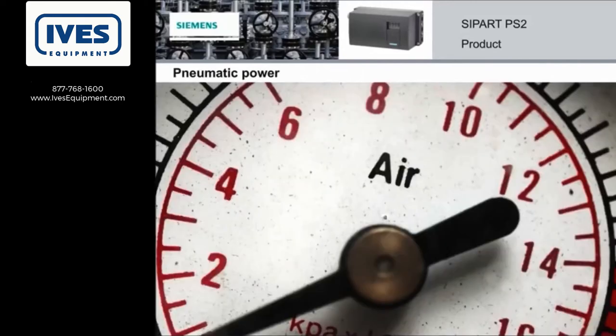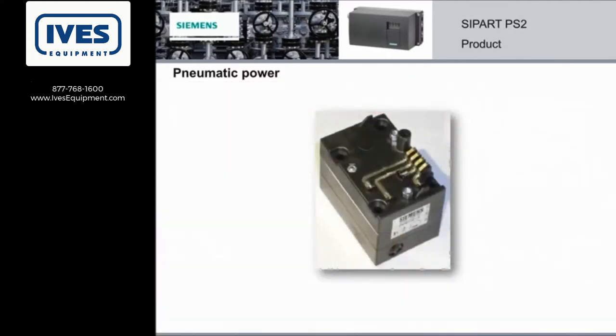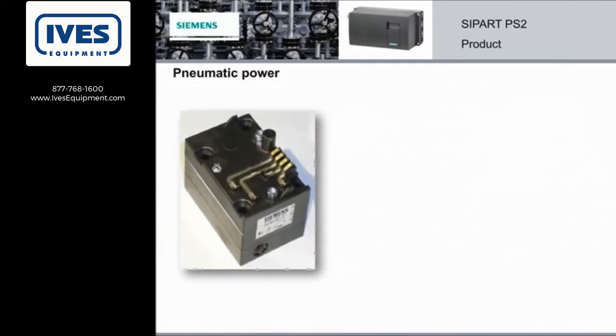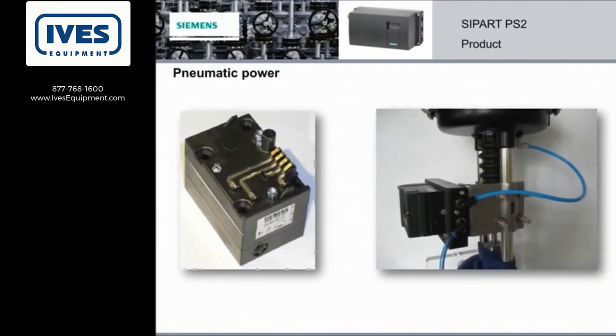The SIPART PS2 is an electro-pneumatic positioner because it controls pneumatic actuators which move valves with compressed air. This is the pneumatic block inside the PS2 that changes the air flow — it uses special piezo-crystal technology. The piezo valves are only activated when there's movement, so there's minimal air consumption. The compressed air comes in, and the pneumatic block in the positioner changes the air flow going to the actuator, which then moves the valve.